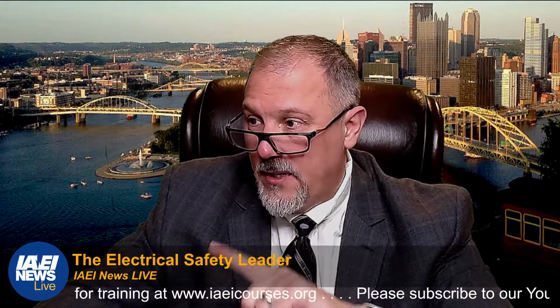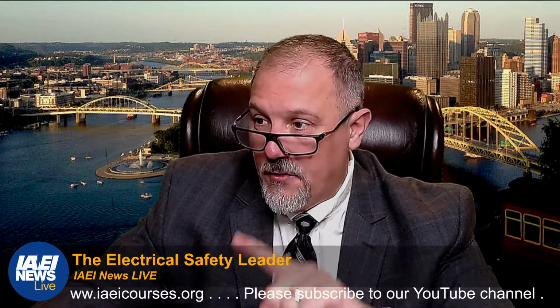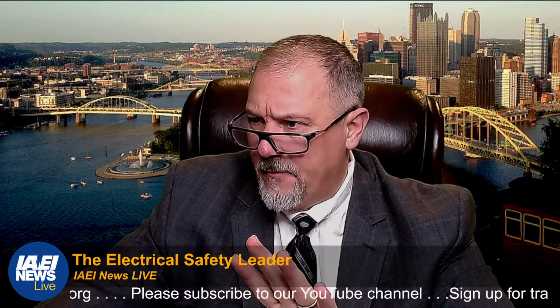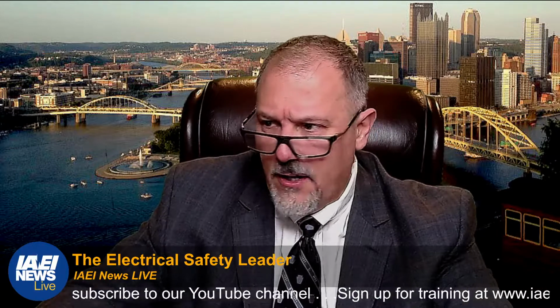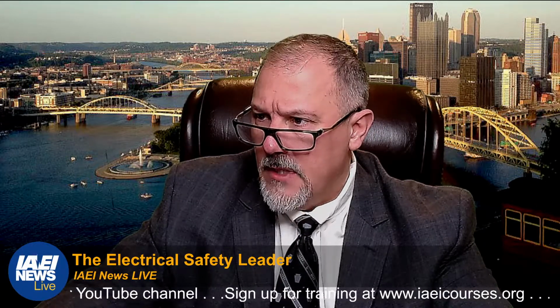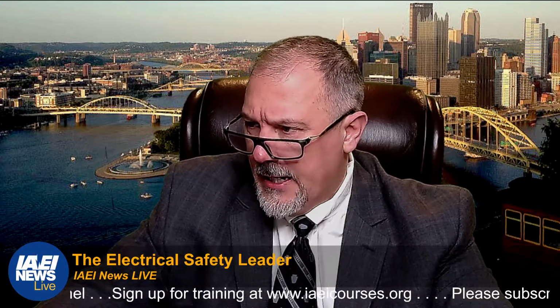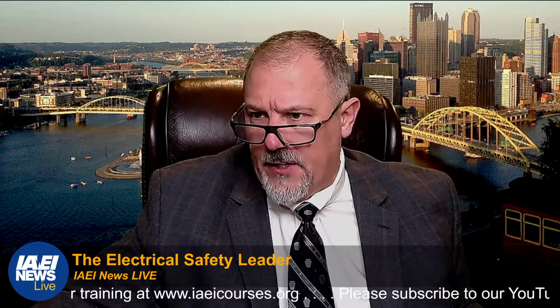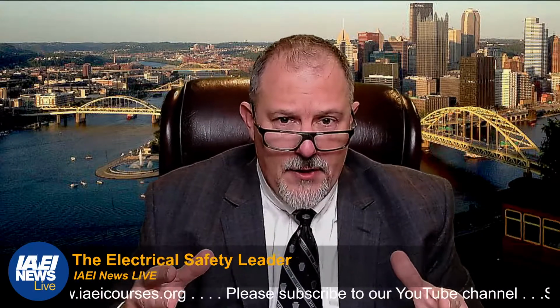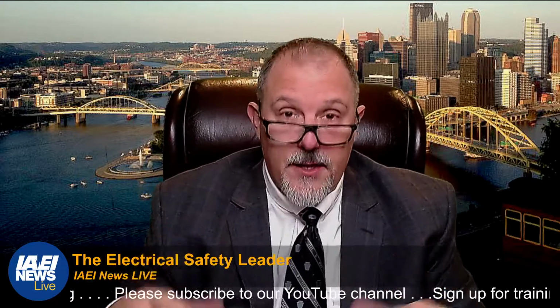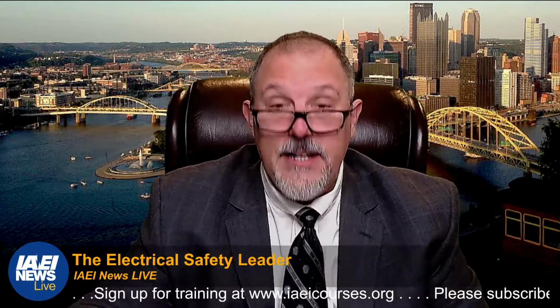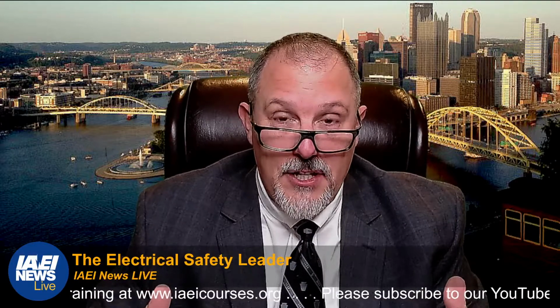Get engaged, get involved. So looking at Article 700 in the 2023 version, 700.3 had a small change. They added an informational note that 700.3(C) is still there, and I don't see a reference to 70B associated with 700.3. But there are other areas in the National Electrical Code that reference maintenance. I just gave you one other case in Article 700. Homework for all of you tonight is to go to the code and find the rest of those locations.